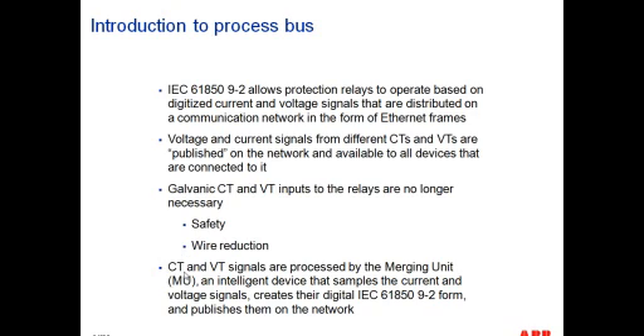It's also important to know that your current transformer and voltage transformer signals are processed by the merging unit, an intelligent device that samples the current and voltage signals, creates their digital IEC 61850 form, and publishes them on the network. So this is a basic summary of what we just discussed.